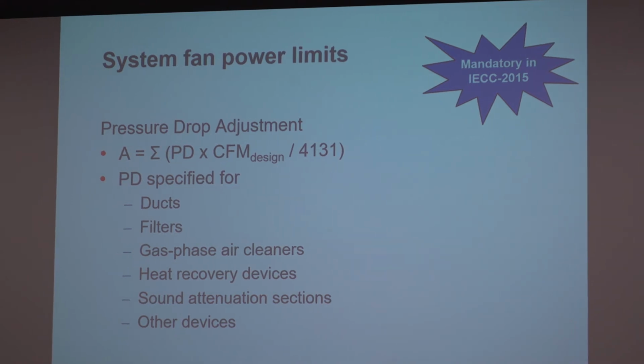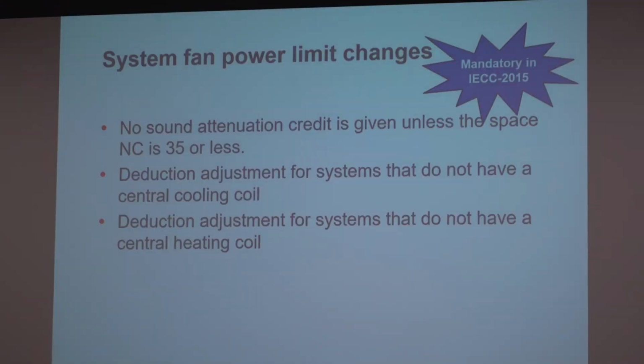The thing that's different between 90.1 and IECC is that you can trade system fan power for something else in 90.1, but you cannot in IECC. So it's mandatory in IECC, and you're basically in the soup if you can't meet it. The things that are different in IECC 2018 and 90.1 2013 is that we started to reduce the amount of credits that you get. So you don't get sound attenuation credits unless you really need a really quiet space. You don't get credits for fully ducted systems unless, oh, that's in the new version. This one has to do with cooling or heating coils. So just makeup air systems without any conditioning don't get a full credit because they don't have pressure drop through the coils.